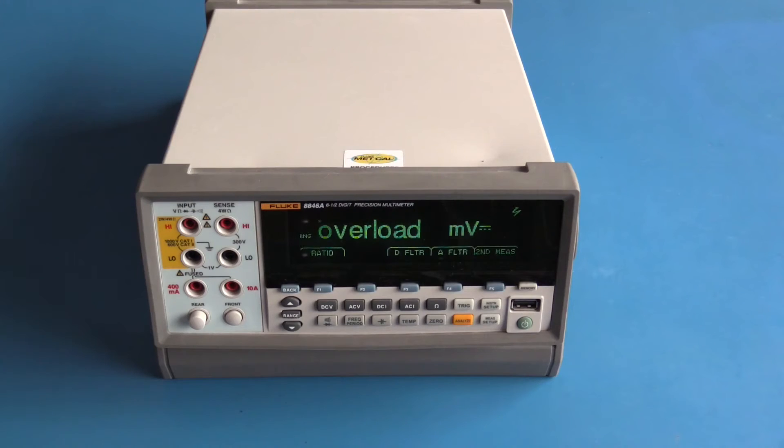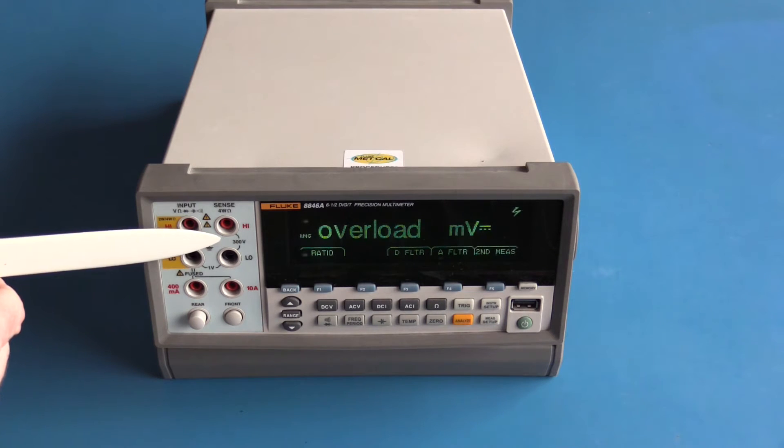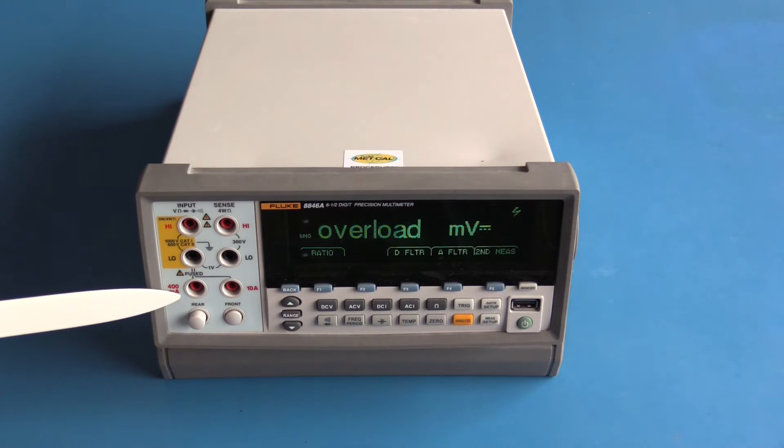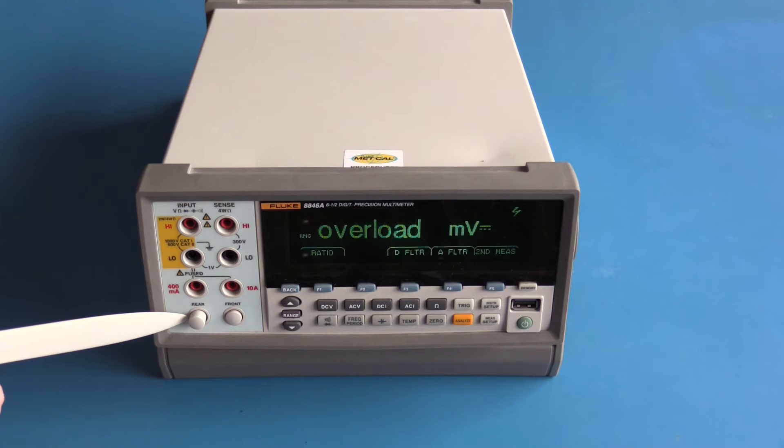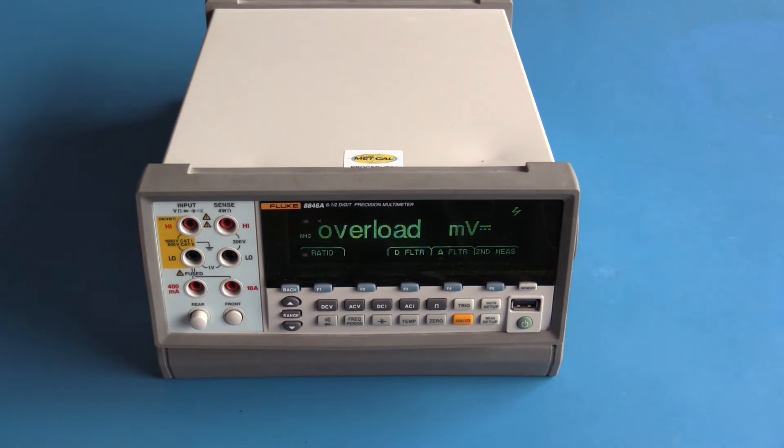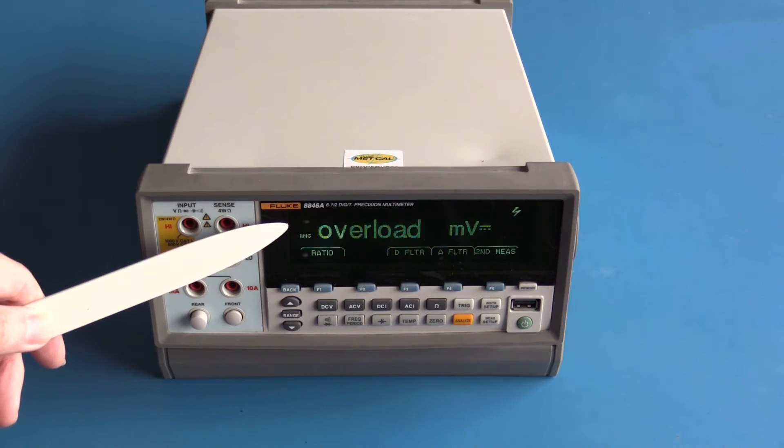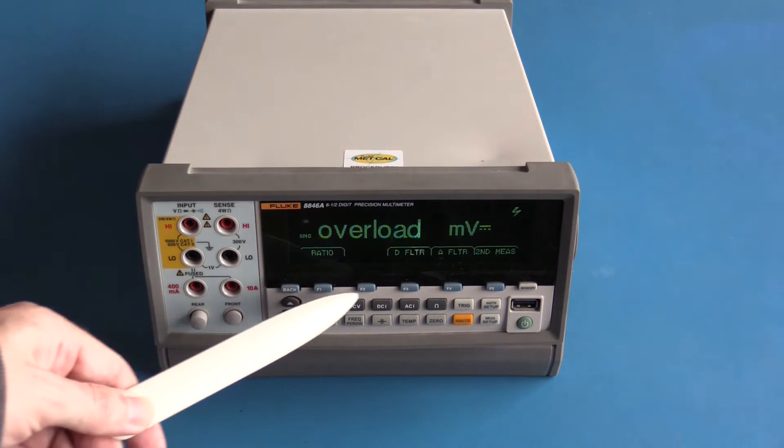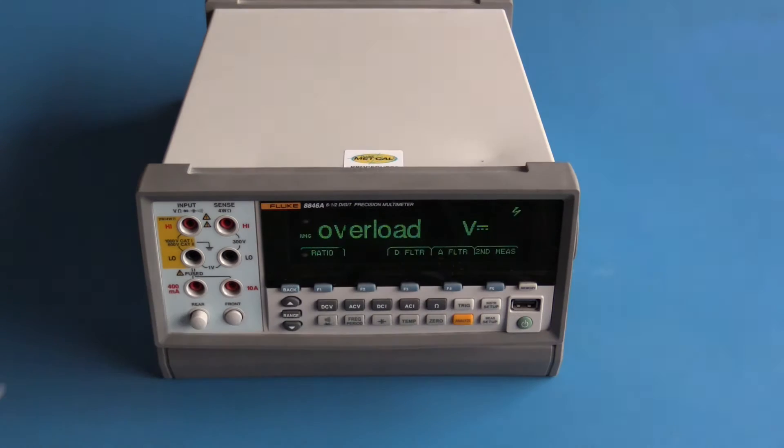So let's take a look at this Fluke 8846a six and a half digit precision multimeter on the bench. At the front of this meter we have our two primary input jacks, our two sense jacks for current measurement, we have the 400 milliamp jack as well as a 10 amp jack. This bench multimeter also has jacks on the back. For the purposes of this review we'll be using the front input jacks.